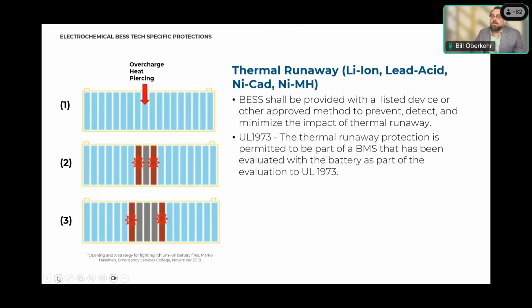Thermal runaway is something that has come up quite a few times in this presentation. Here's a very crude illustration of what that actually looks like. It is important to understand that once thermal runaway is initiated, it is an exponential rise in heat that cannot be stopped. So you can't reverse it. All you can do is contain it. So thermal runaway can spread to adjacent cells. This is what we're testing for in the cell level 9540A large scale fire test, to see to what extent that thermal runaway propagates from cell to cell. Certain BMS systems are able to isolate problematic cells and shut it down with the intent of being able to control these thermal runaway incidents should we be unlucky enough to experience one. Next slide, please.